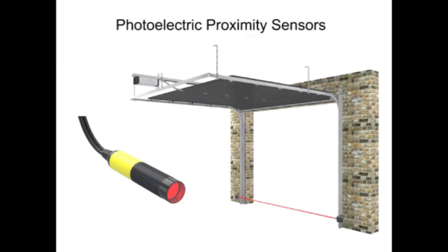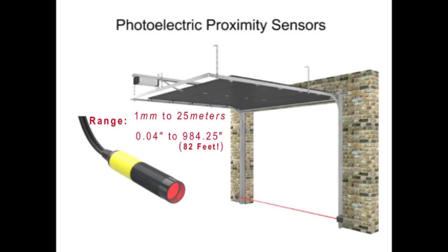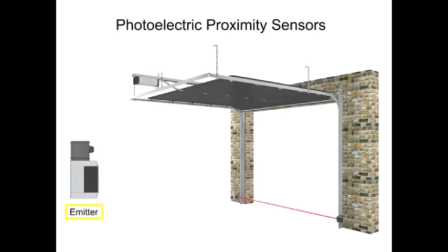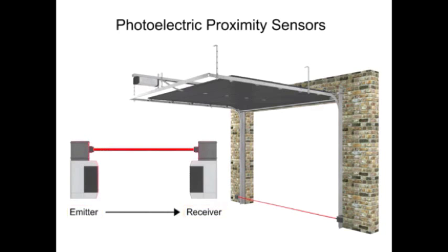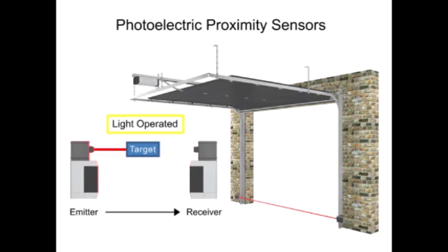Photoelectric sensors have the greatest detection range, from 1mm to 25 meters or more. They operate by the use of an emitter, which transmits a beam of light to the receiver. When the light is normally being received, it is known as dark-operated mode. When the absence of light is required, it is known as dark-operated mode.